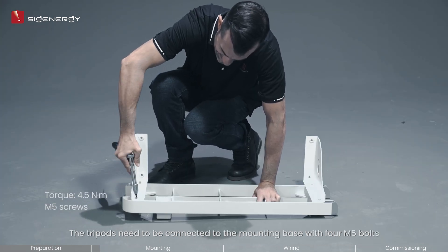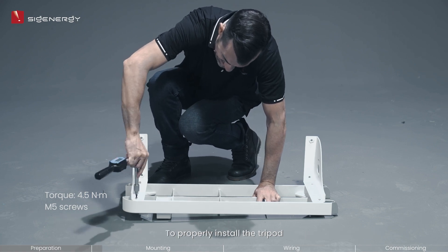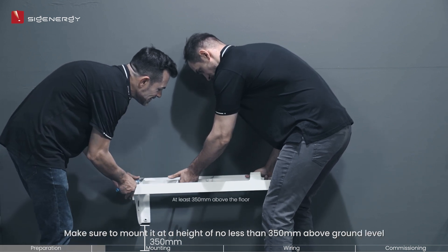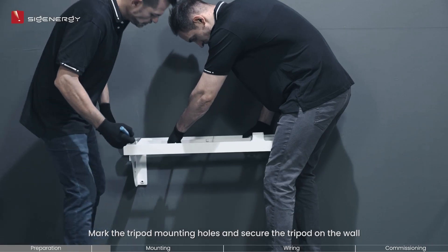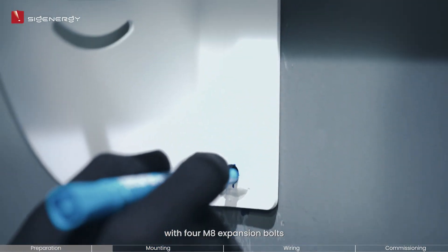The tripods need to be connected to the mounting base with four M5 bolts. To properly install the tripod, use four M8 expansion bolts to secure it onto the wall. Make sure to mount it at a height of no less than 350 millimeters above ground level. Observe the horizontal bubble to make sure that the base is completely level; if not, adjust the placement until leveled. Then mark the tripod mounting holes and secure the tripod on the wall with four M8 expansion bolts.